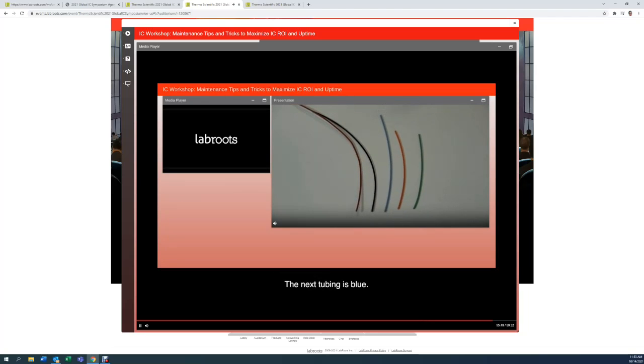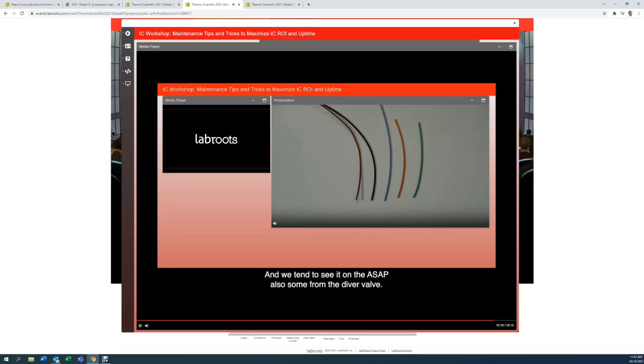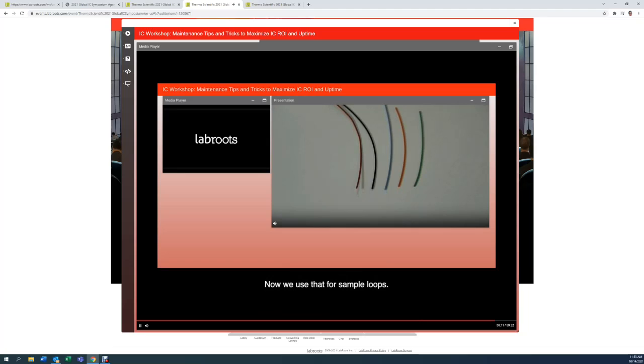The next tubing is blue. The blue tubing is about 15/1000th of an inch, and you'll only actually really see it in one place. And we tend to see it on the ASAP autosampler on the divert valve. The next tubing is the orange tubing. That's 20 thou in internal diameter, 20/1000th of an inch. Now, we use that for sample loops. So something like a 25-50 microliter sample loop will probably be made out of orange tubing. So we use it when dead volume isn't important, but we just need a bit more volume in the tubing.